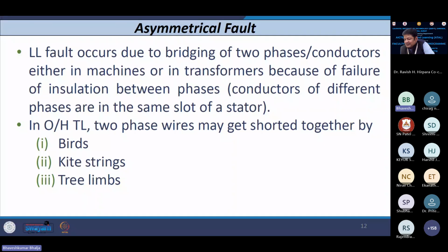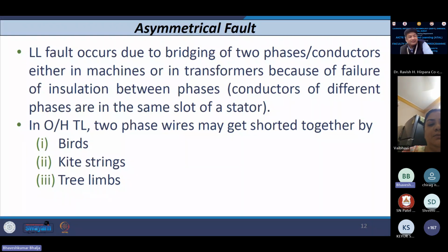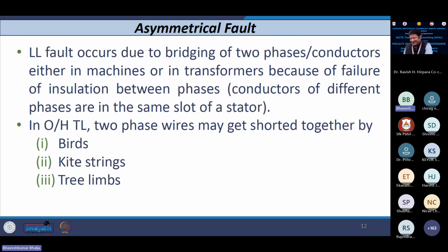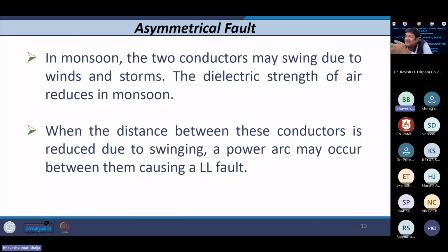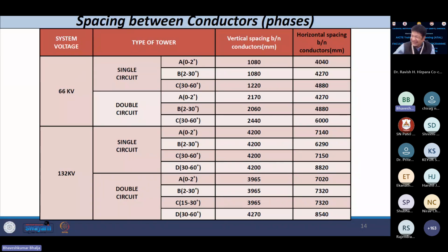And if you consider the asymmetrical fault, a line to line fault occurs because of the bridging of two conductors. It may happen in machines, let's say AC, DC or any other machines, or it may happen at the terminal of a transformer, or because of failure of insulation between the two conductors. We know that during the monsoon season or some specific condition, let's say when there is a cyclone and the wind is very severe, the swinging of conductors takes place, and this may create a line to line fault. However, a line to line fault is not going to occur because of birds, kite string or tree limbs, right? Because the height of the conductor is very high. And if you look at the spacing among the different phases at different voltage levels, 66 kV, you can say.